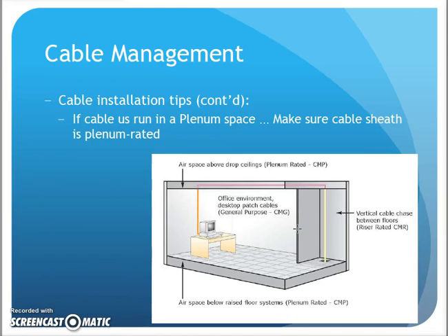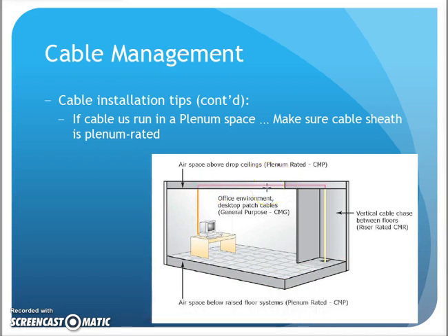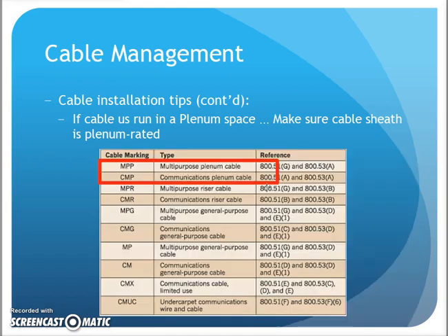If I'm installing cabling in a plenum space, okay, is the space above like a suspended ceiling or below a floor? If I'm installing cabling below a floor or above a suspended ceiling, that's a plenum space. If I install it there, I need to be using plenum-rated cabling.